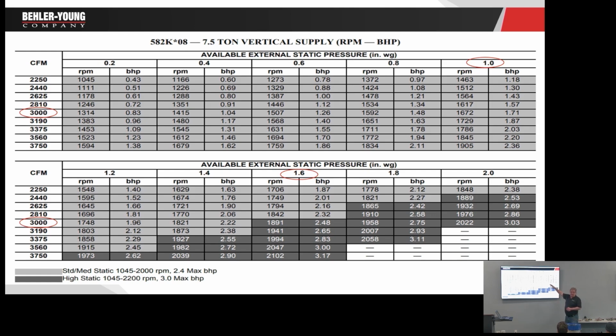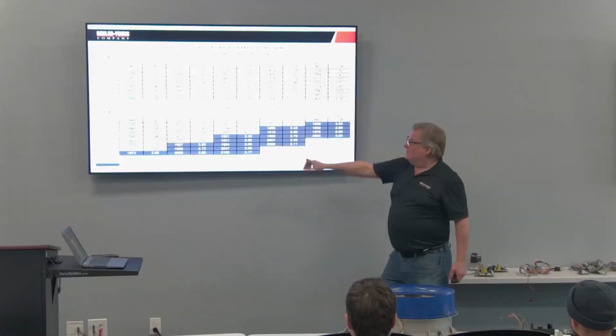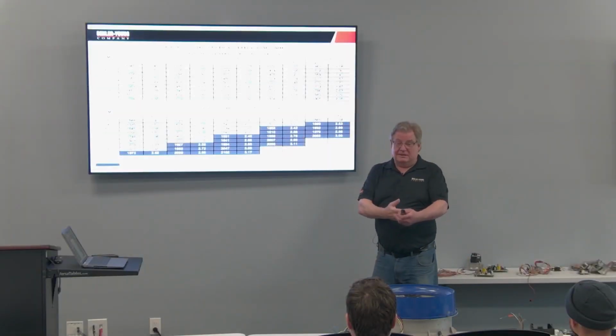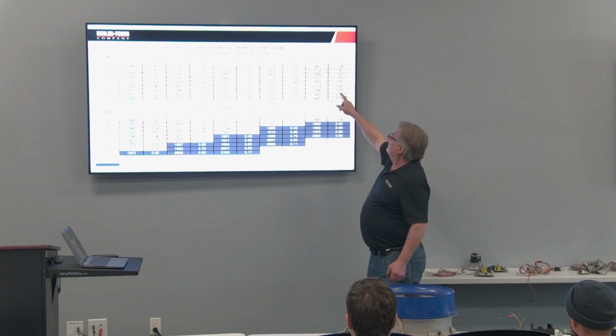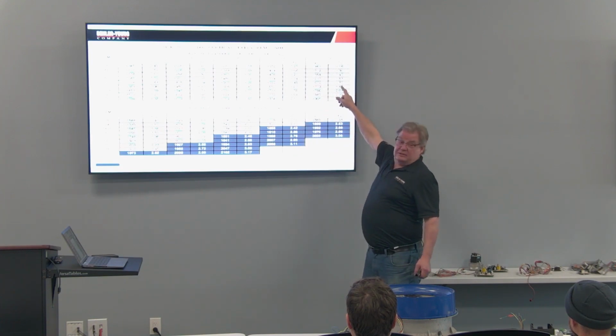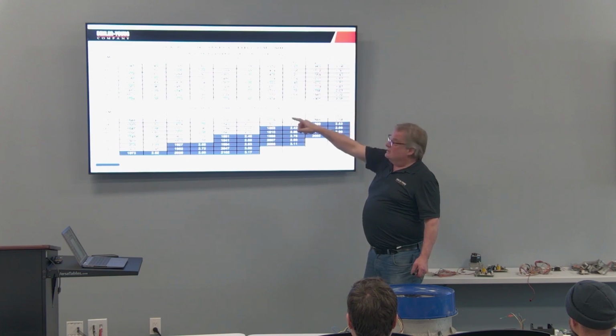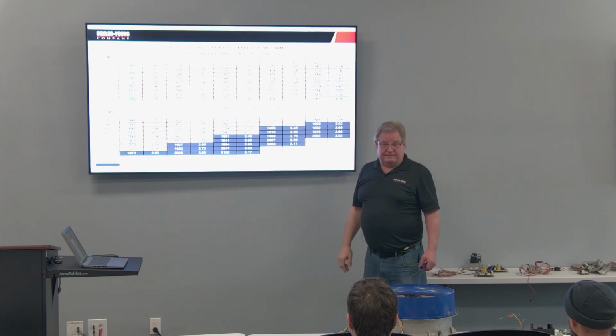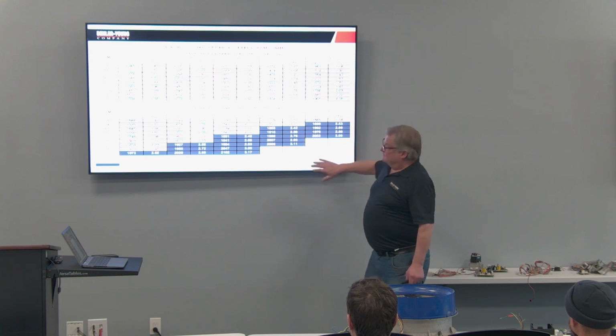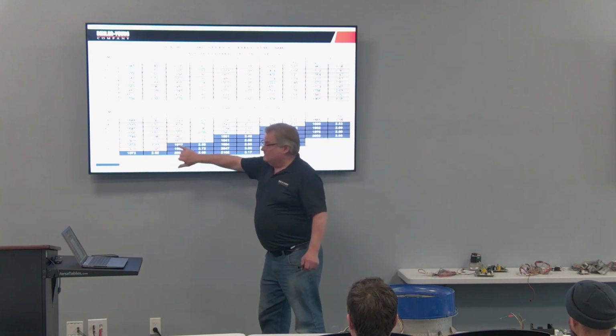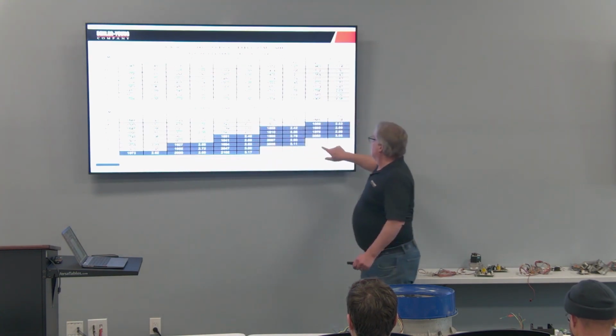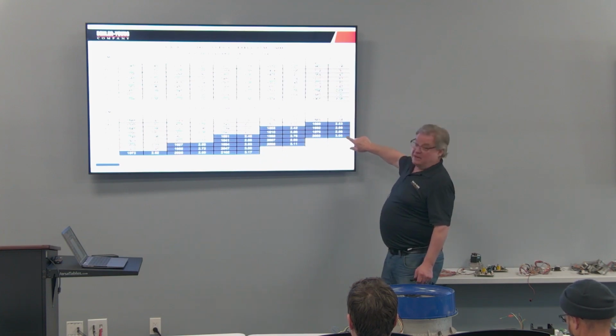It could be your duct system is too much static for your unit. And if I did my static, okay, my static's 1.6, I pull the document on this unit, well, shoot, it only goes to 1 inch on the medium and standard static. I have 1.6 inches. I'm not going to get 3,000 CFM. So I'm freezing coils, I'm tripping limits. All right. The high static unit is in dark gray. Well, hell, look at that one, has no problem giving me 3,000 all the way over to 2 inches.